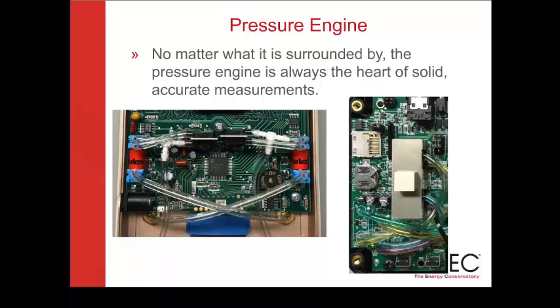On the left you see the DG-700 pressure engine with the auto zero valves on the left, and the upper center you'll see the two sensors. For the DG-1000 we have them encapsulated inside a metal case to increase the ability of the gauge to reject electromagnetic interference and radio frequency interference.